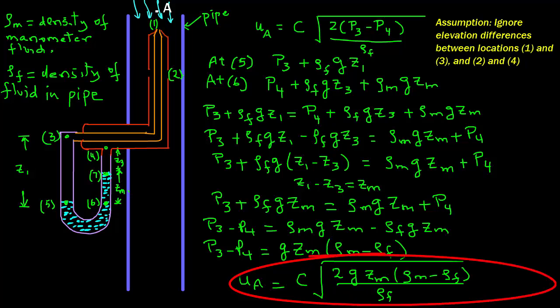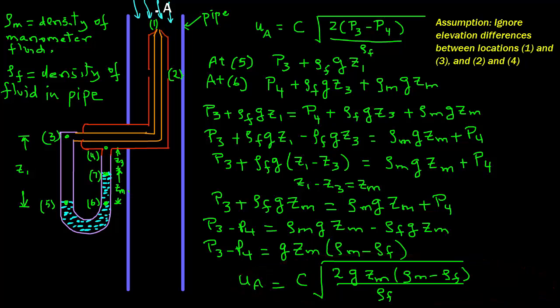We can now substitute this expression for P3 minus P4 into the velocity equation from the previous tutorial. To use this with a manometer, we need to know the displacement of the manometer fluid Zm, as well as the densities of both the manometer fluid and the pipe fluid. Using this expression, we can calculate the velocity Ua at location A. Note that this is the point velocity, not the average velocity. To find the average velocity with a Pitot tube, we would need to measure velocity at several points across the pipe, and there are methods to do that which will be covered in a different tutorial.